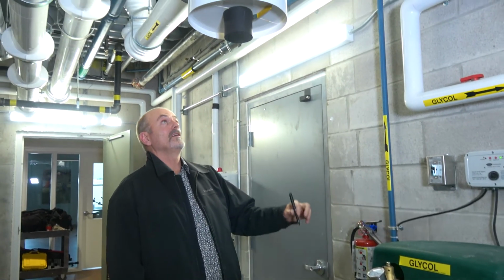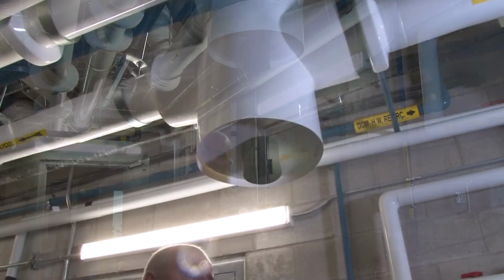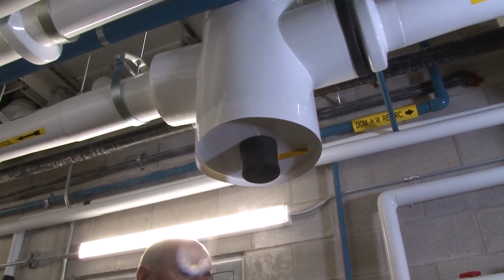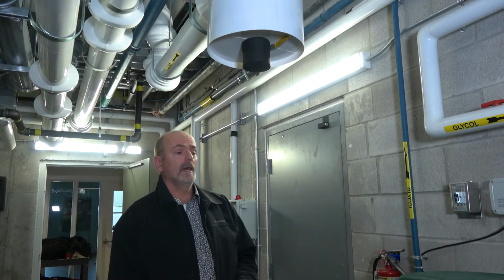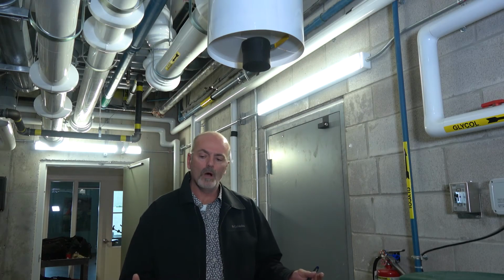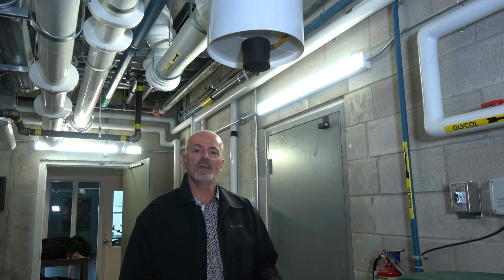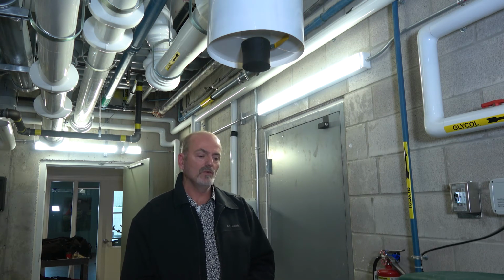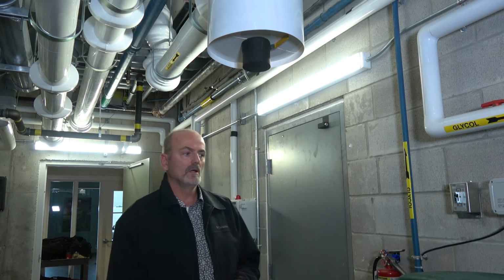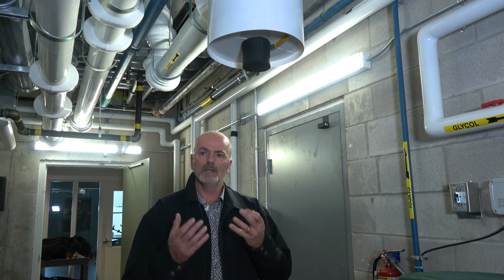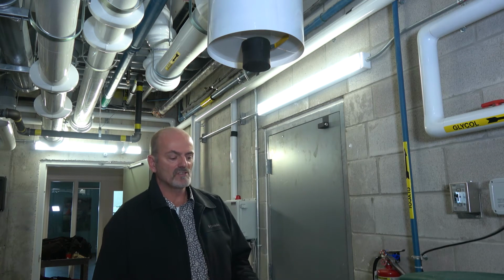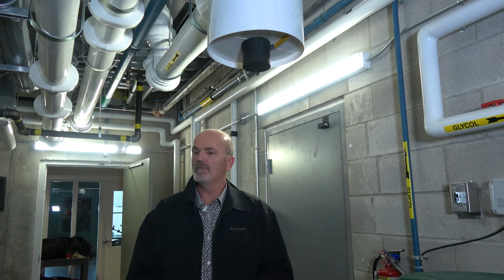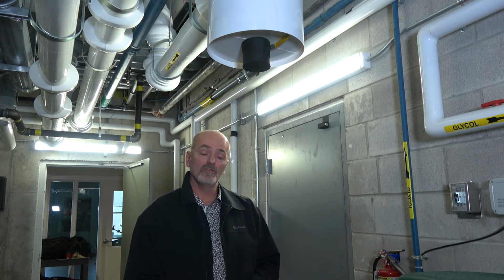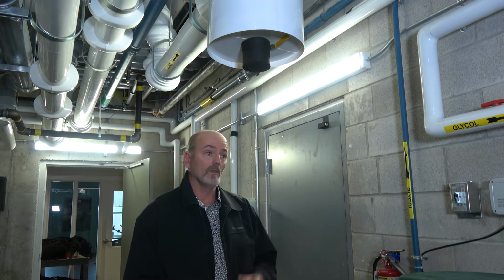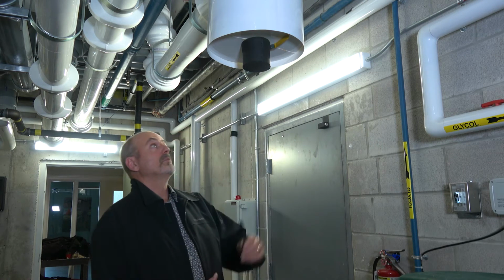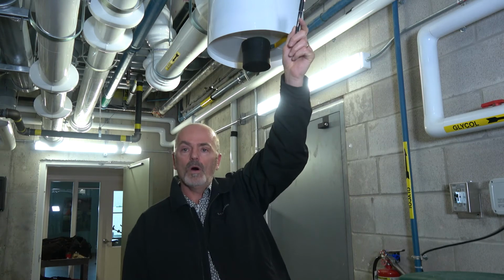The device we're going to look at here now is what's known as an air separator. In this case, it's a higher end micro air separator. The purpose of this device is that all water glycol contains air. When you put that water glycol into a closed system, and as you heat it and cool it, it expands and contracts, you have to try and remove the air from the system. The reason we need to remove the air from the system is because it can create issues with the system. We won't bother getting into that, but this device allows for, in this case, the water glycol mixture to run into the tank.